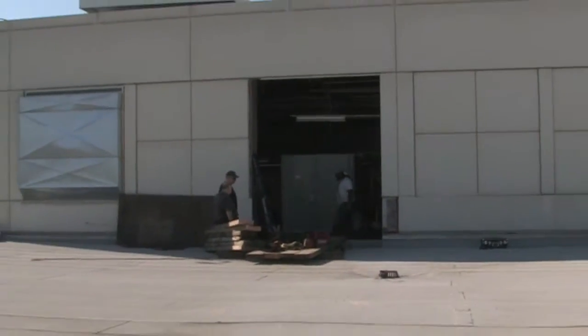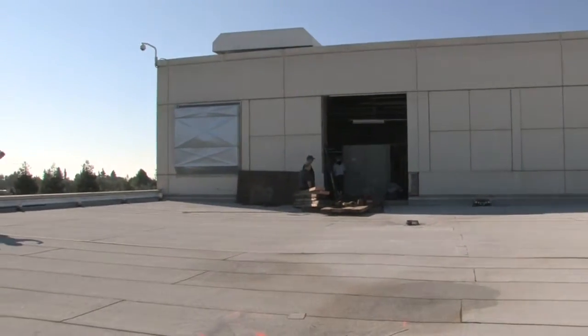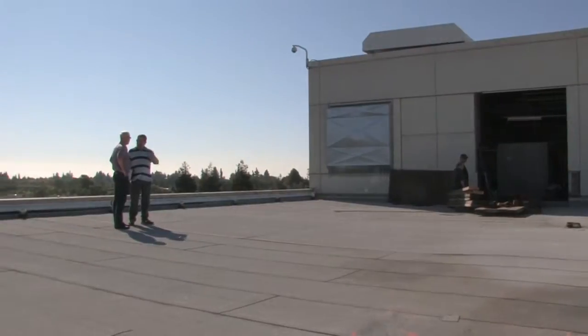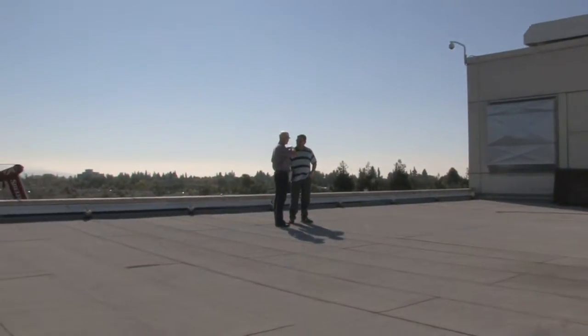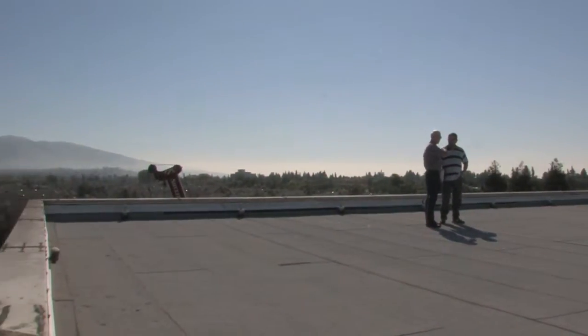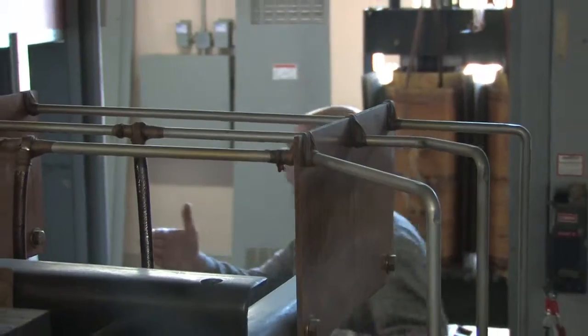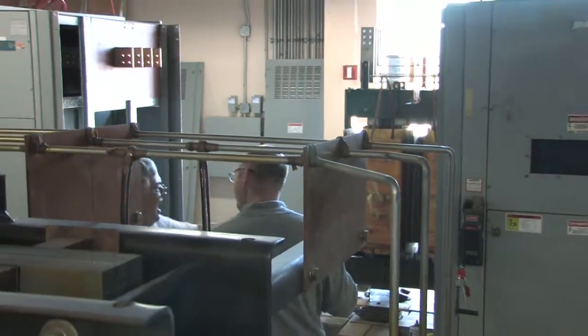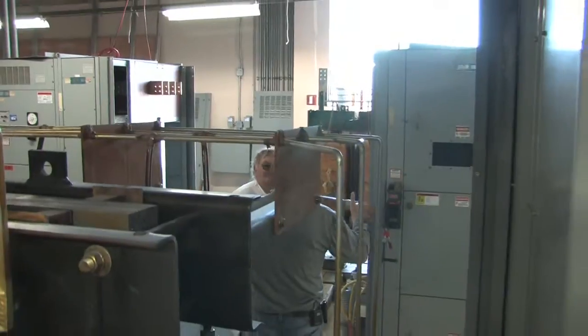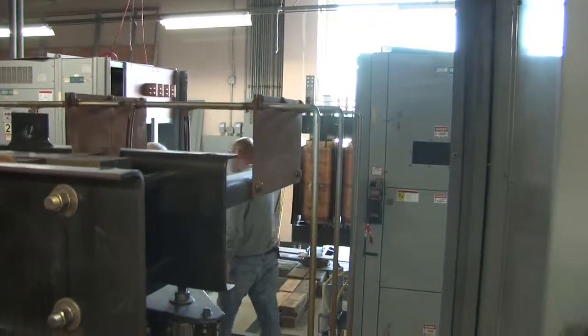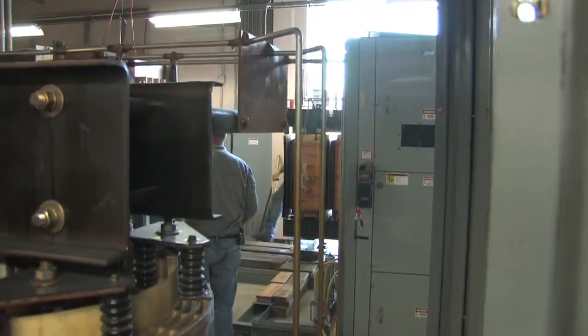And in order to get that out, the process was we first had to disconnect and get the 1500 kVA transformer out, take the top of the switchboard apart, and get it out of the way. That was the only way it would physically fit through that opening, through the switchboard and then out to the roof to fly it downstairs.